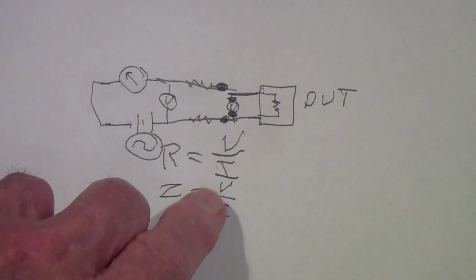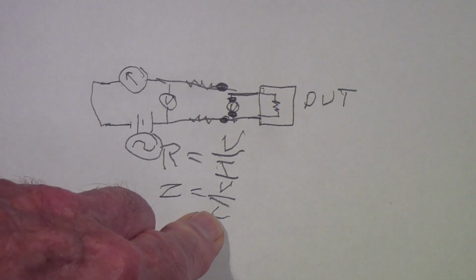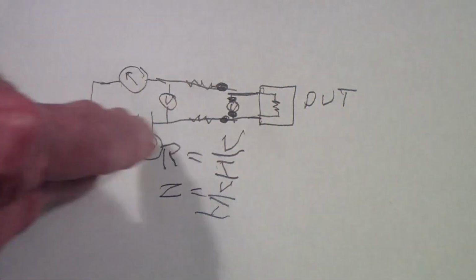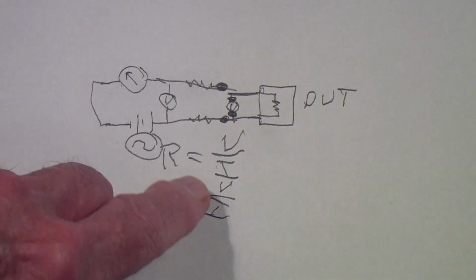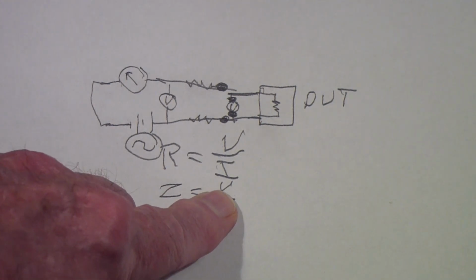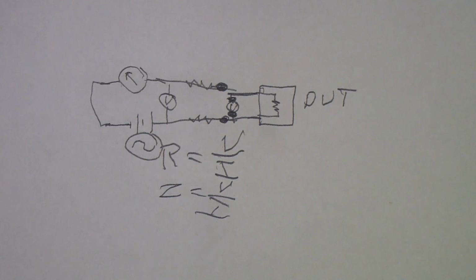But to do that, you need an accurate measure of the current, which is easy because the current is the same throughout the loop. But you also need an accurate measure of the voltage, which is why you need the second pair of wires in a 4-wire system.